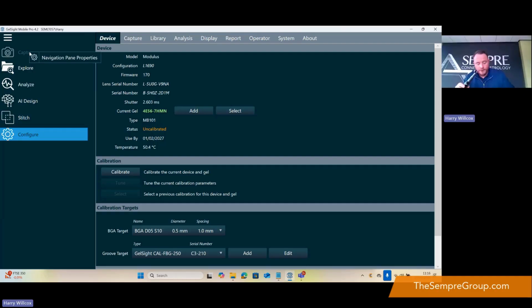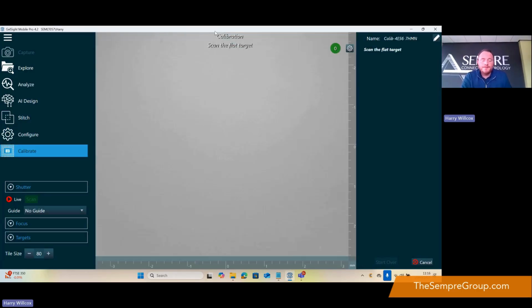Okay. So I can take my artifact, and the artifact now has different attachments depending on whether you're using the 90-degree or the straight probe. I'm using the 90-degree, so I'm going to snap this on top of my artifact, and I'm ready to calibrate. The calibration detail has already been inputted into the system, as it comes with a certificate for the artifacts that we get. So I can click to calibrate.